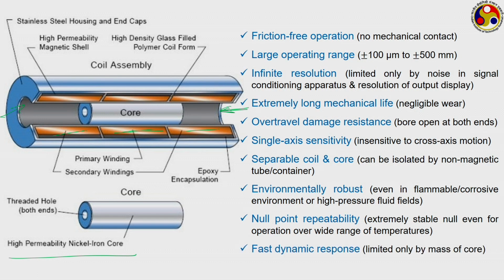The dynamic response is very fast. It is limited only by the mass of the core itself, and that mass is generally very small, so we get quite a fast response. Again, the response that we actually get depends on the resolution and the response of the voltage measuring instrument. And finally, we are talking about absolute output here. Even if there is a loss of power during operation, whatever the last position of the core was, it will remain in that position, and as soon as the power is back, it will start to operate again.